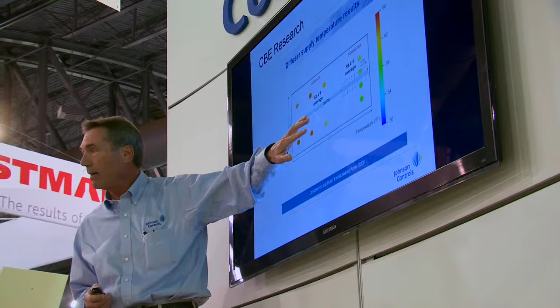It's also reflected in the new ASHRAE guide. Other approaches could be multiple injection points in a floor plate to help get that air out there, or multiple air handlers, floor by floor. Lots of ways to skin the cat. But the idea, again, is to maintain consistent temperature, cool air to the perimeter, that's the basic idea.